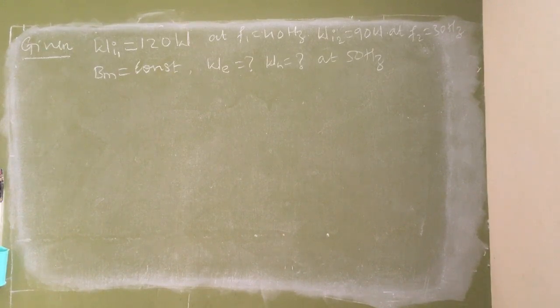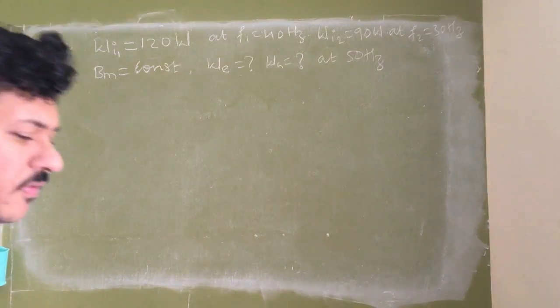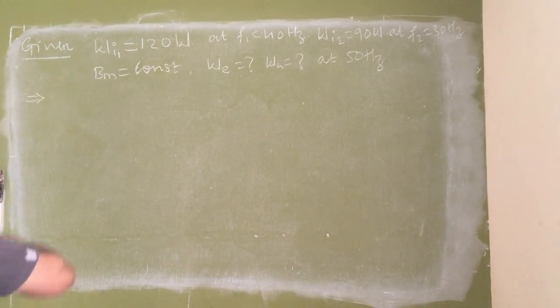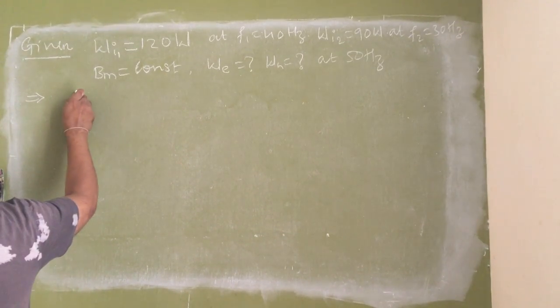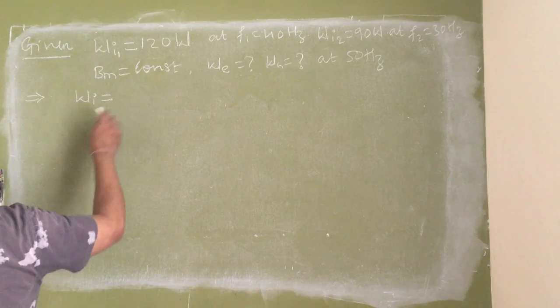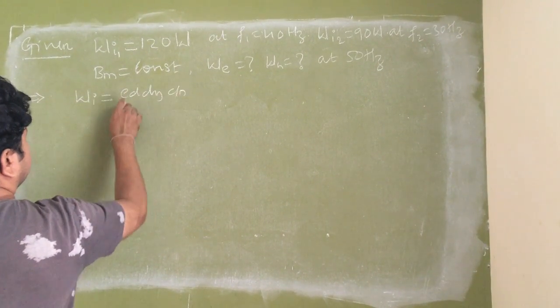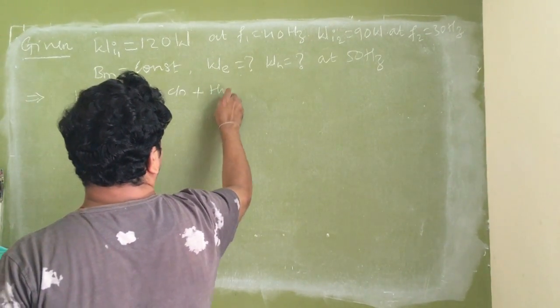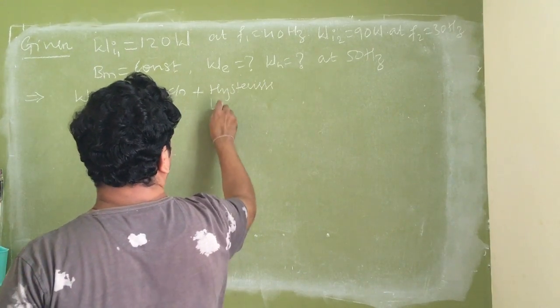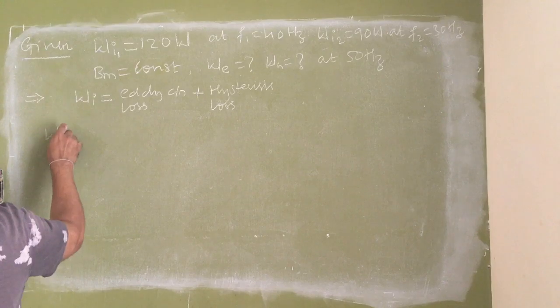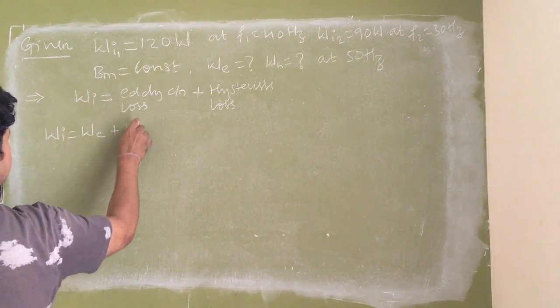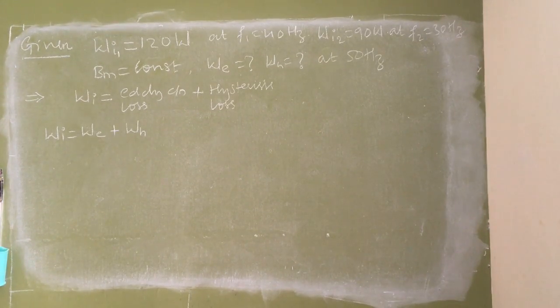So the iron loss in a magnetic material is 120 watts at 40 hertz and 90 watts at 30 hertz. If the flux density is kept constant, what will be the eddy current and hysteresis loss at a frequency of 50 hertz? Solution. We know that iron loss or core loss is nothing but the sum of eddy current loss and hysteresis loss. So I can write Wi is equal to We plus Wh.